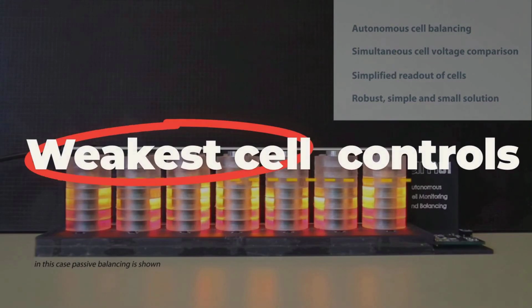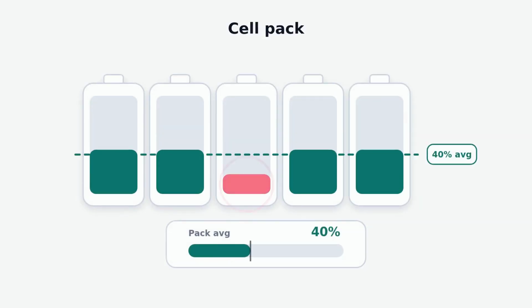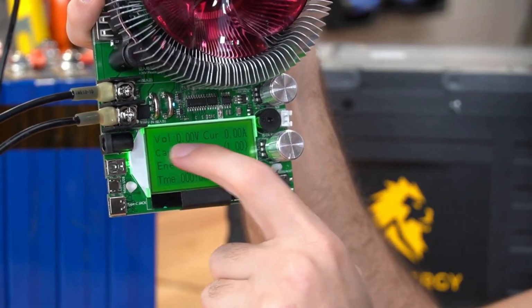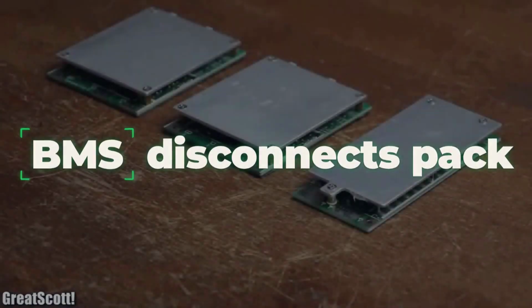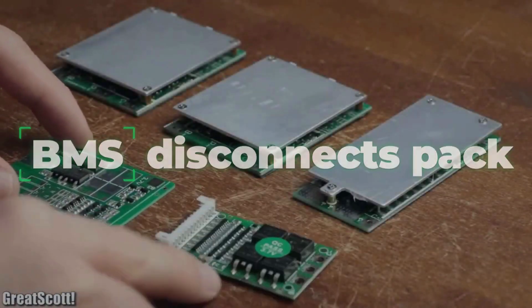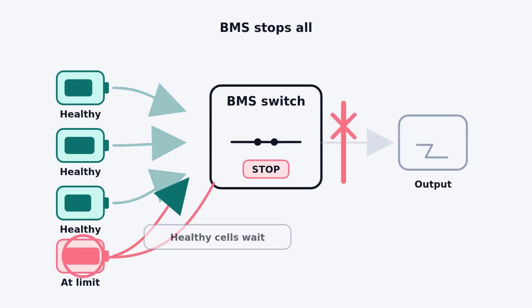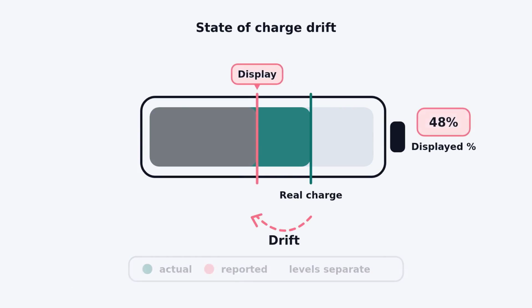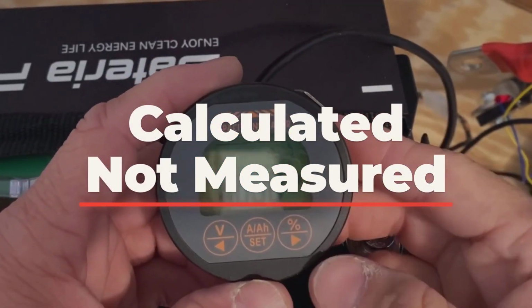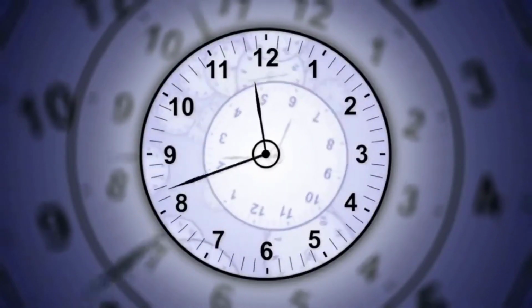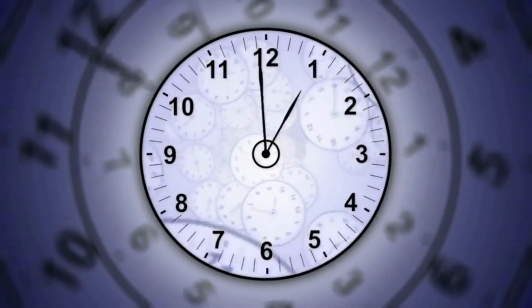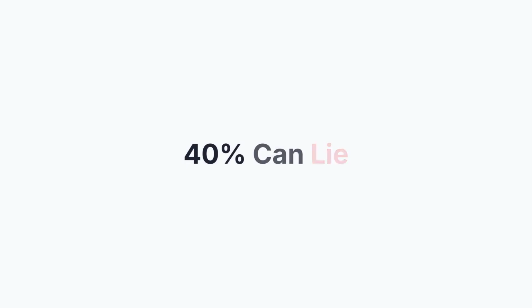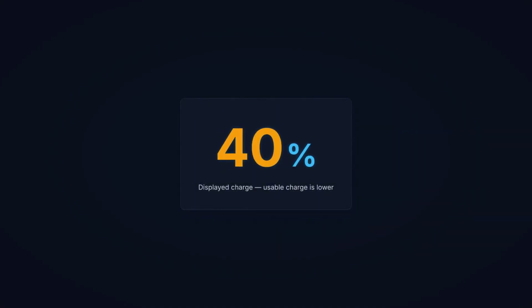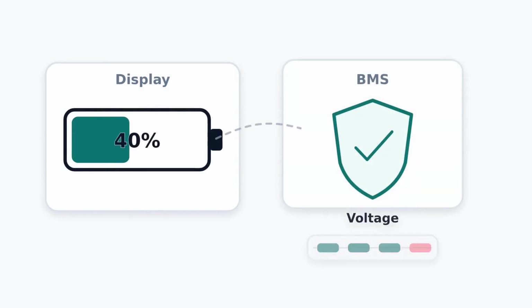Second, cell imbalance. A pack is only as strong as its weakest cell. The overall voltage might average out to 40% remaining, but one degraded cell inside that pack is already at the floor. The BMS disconnects the entire pack to protect that one cell. The other cells could keep going. They do not get the chance. Third, state of charge drift. The percentage on your screen is calculated, not measured. Shallow cycling, missed full charges, and long periods without a proper calibration pass all allow that calculation to drift. The display becomes confidently wrong. It shows 40% while the actual usable charge is lower. You trust the number. The BMS ignores it.